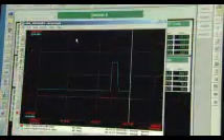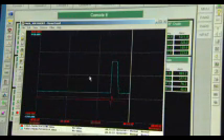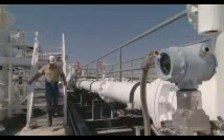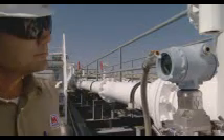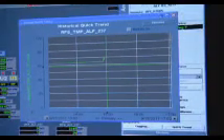In addition to the SCADA system, many control rooms also use fast, highly sensitive computational pipeline monitoring, or CPM systems, to help detect leaks. As liquids are pumped into and out of pipelines, CPM systems continuously analyze the volume and physical properties of liquids, like temperature and viscosity. This data is used to compare actual conditions with expected conditions, giving controllers another tool for monitoring the integrity of a pipeline.